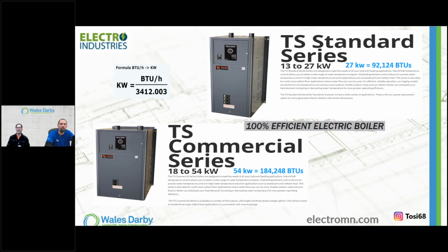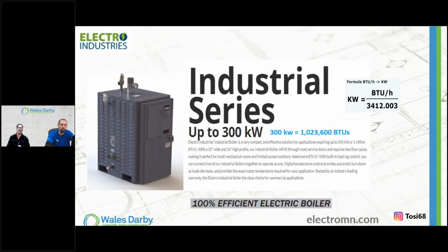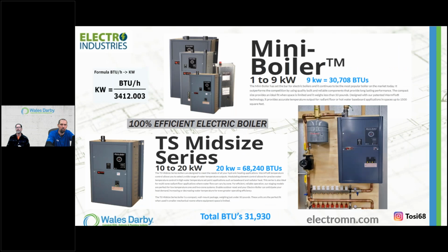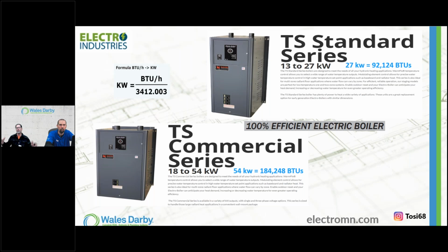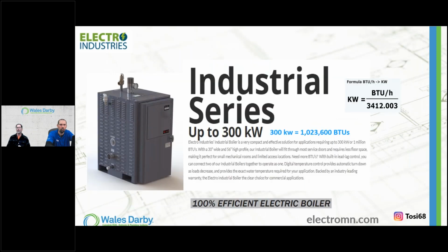So here we go, bigger and bigger. We can go up to 27 kW, we can go up to 54 kW, we can go up to 300 kW, and most of these cabinets are going to increase capacity. So same size footprint, but now going from 1 to I think 16 kW at that first size, and then going up to like 27 or 28 with here. We're going to collapse a little bit of SKUs, but yet gain more capacity by adding more to the vessel. I believe this one here is 1 million, and they're going to go upwards to 2 million. Can you imagine? This is pretty wild stuff to think about powering, right? But what's the byproduct here? There's no flue. There's no need for gas, no need for primary, secondary, no need for really maintenance. Water quality, again, is always going to be around us. Be cautious of water quality, right?